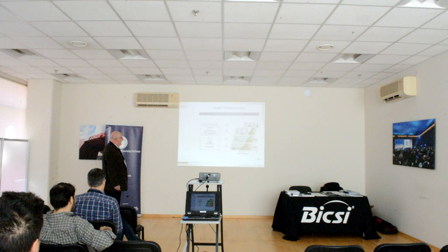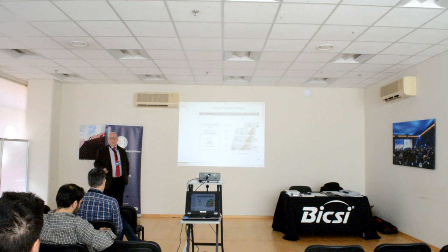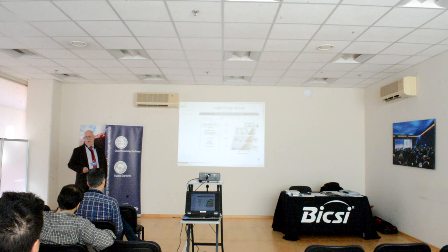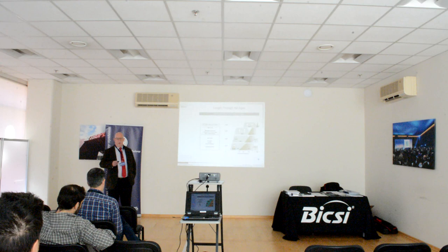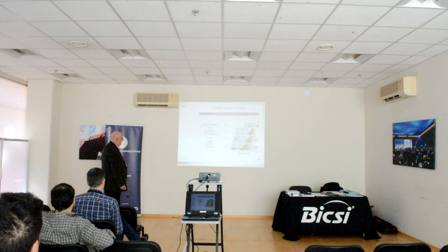And now we're at the point now where, to be honest, if I was installing a building, if the distances were more than 100 metres, I would probably start thinking very seriously about mixing single mode and multi-mode at those in excess of 100 metres. Because we have actually got to the point now where everybody's focused on 100 metres on fibre, just like they were or are on copper.